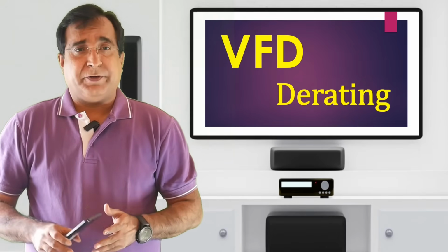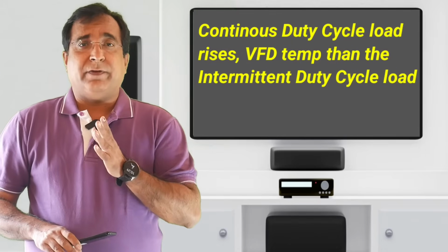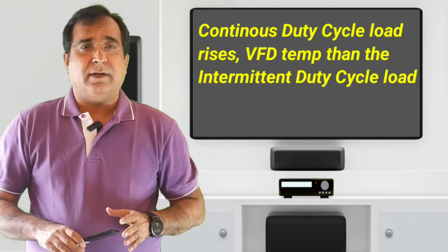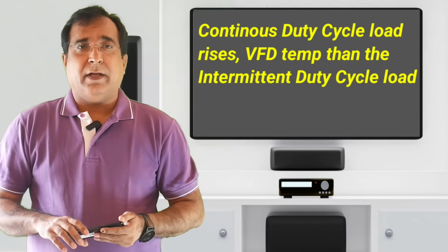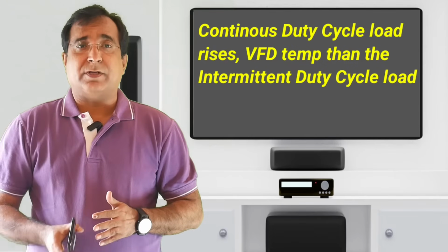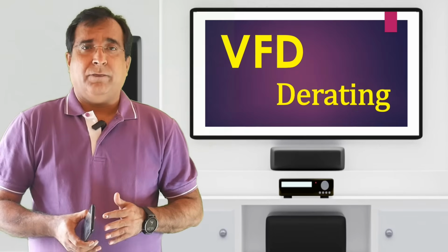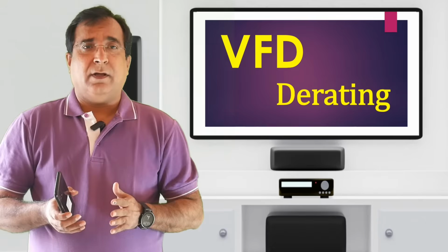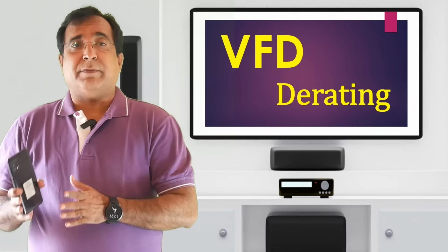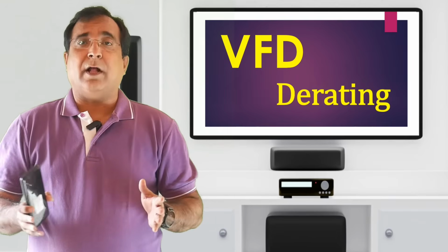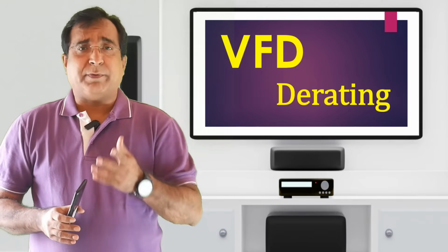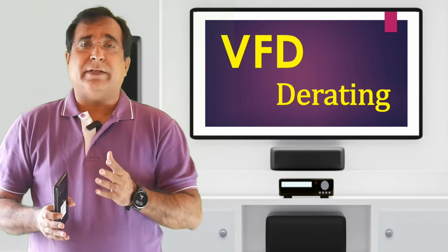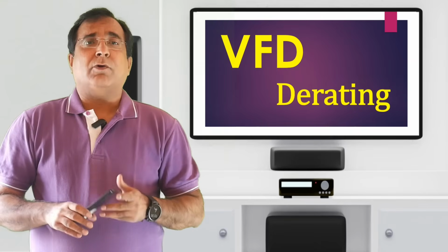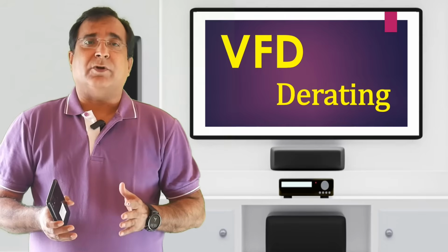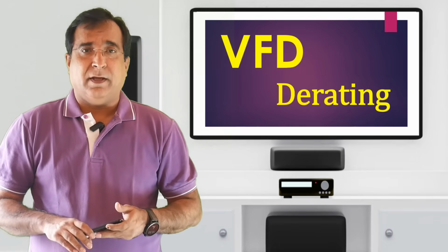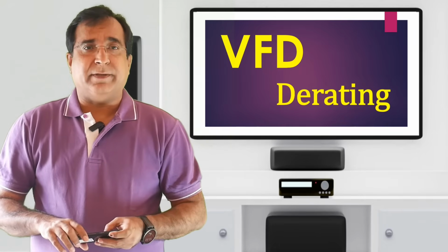The next factor is the VFD duty cycle. Is the load on the VFD continuous or intermittent? It depends on the application of the VFD. If it is a continuous load, the increase in temperature causes the VFD to derate when compared to intermittent duty cycles. Operating a VFD near maximum rated capacity for an extended period of time may also result in overheating. The problem of overheating can be solved by derating the VFD here also. Poor power quality, such as voltage spikes or harmonics in the power supply, can affect VFD performance. Here too, this can be handled by derating the VFD.